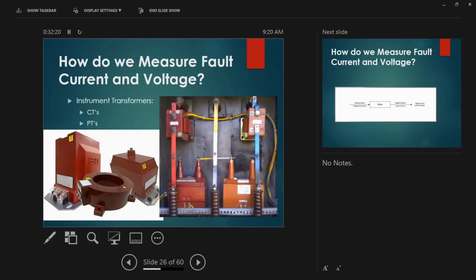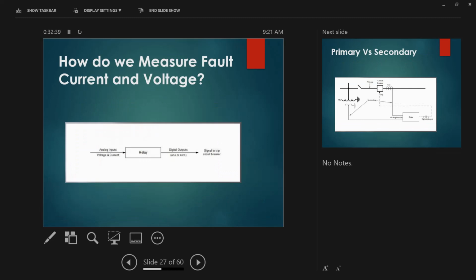And this is the picture. Sometimes we undo the cable on this side just to do the turns ratio. Make sure that you put it back properly and tight enough to do its work. CT VT. Now, how do we measure the fault? So that's it. Analog input, voltage and current, to the relay; digital output, close or open, a signal to trip the breaker.